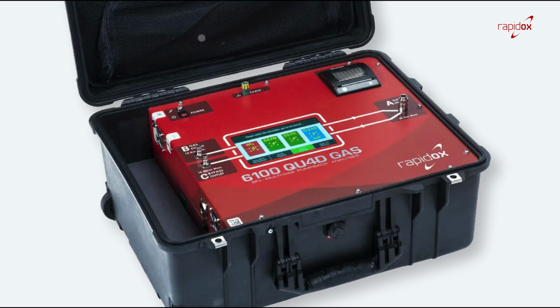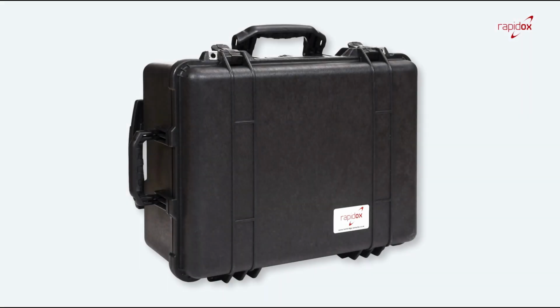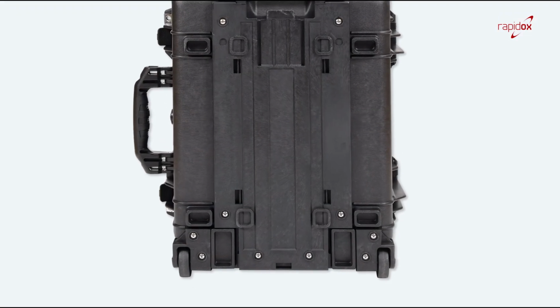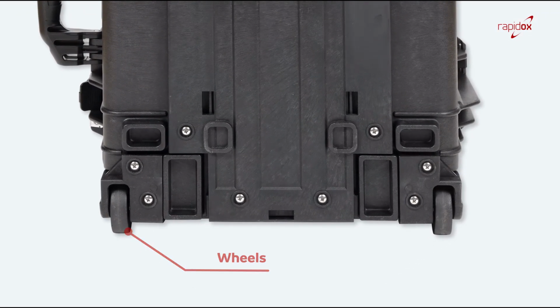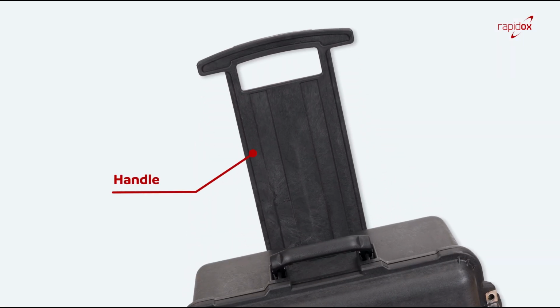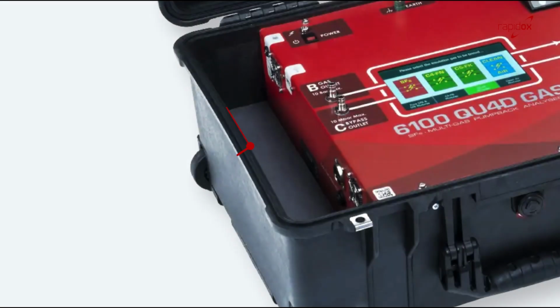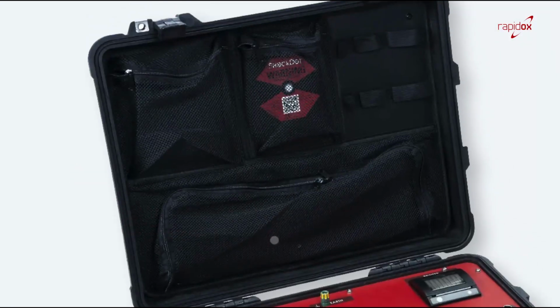First thing to say is that all our pump back analyzers are housed in a waterproof Pelican case. This is a genuine Pelican case, and this particular version has wheels and a handle that can extend, so you can carry this around or drag it behind you to locations to do your testing. The case has got a compartment here where we store the DILO couplings and other things, and we've got some storage area up in the top of the case to house the hoses and other accessories that we supply with every instrument.